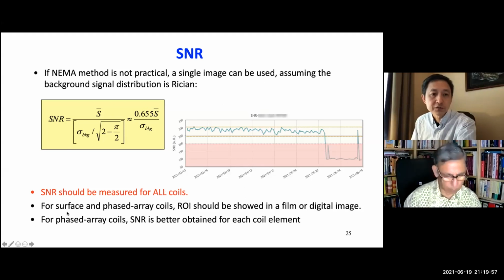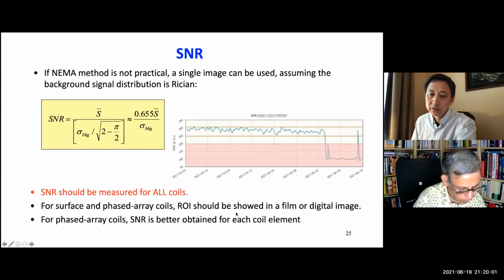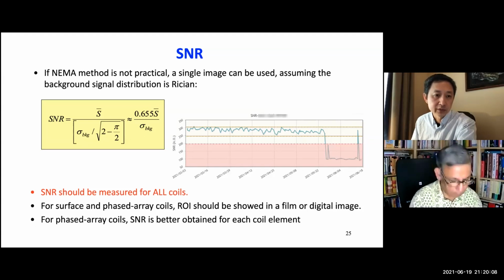For surface and phased array coils, the ROI should be shown or documented. So we make sure we are making the measurement at the same spot every year. And for a phased array coil, because there are many elements, SNR should be obtained for each coil element.